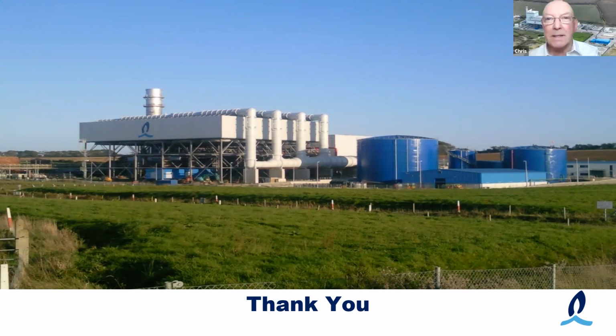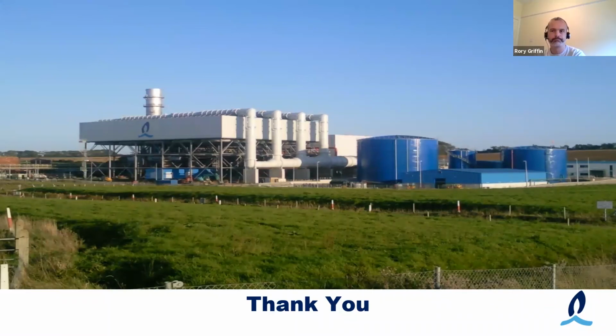Okay. Does the station always output 450 megawatts? No. How many generator sets are in the station? So it's a single shaft machine, so there's only one generator. That's probably something I should have touched on. Other configurations might be a dual shaft machine, which would have a generator on the gas turbine and the steam turbine, and the output then is collected, I suppose, at the step-up transformer. But at Whitegate, it's a single shaft arrangement, so only one generator.